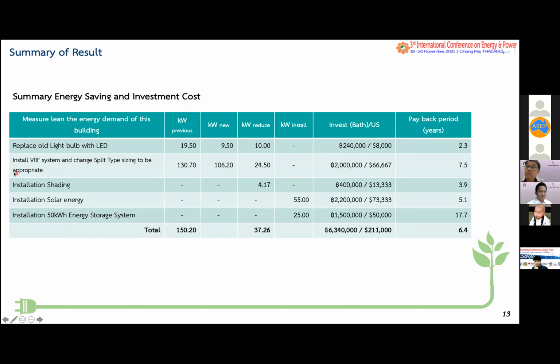For changing the air conditioning to a VRV system and revising some cooling load, we can reduce the power demand of the air conditioning system from 130 to 106. And with the investment cost of about $66,000, the payback period is about 7.5.